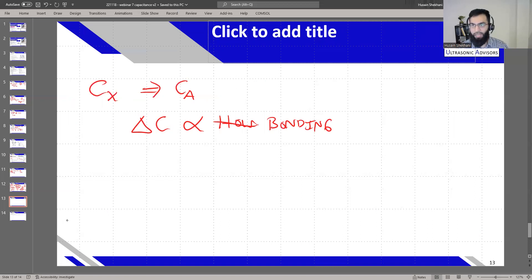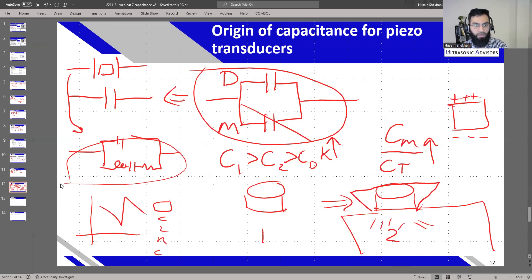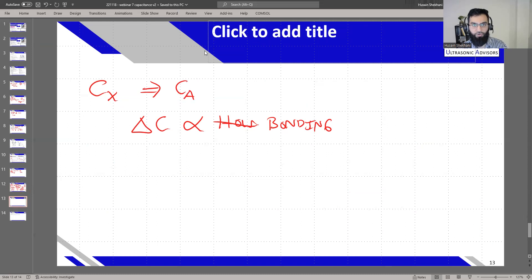One practical application: measure capacitance of the crystal before assembly, then measure capacitance after assembly. The change in capacitance can be correlated to bonding condition. Generally, the better the bond, the lower the capacitance — though it won't reach zero because the mechanical component is never fully eliminated. So whenever you assemble — whether in a bolt-clamped Langevin transducer or otherwise — the capacitance is reduced, and that reduction becomes a way to judge assembly quality. If two identically built transducers show different capacitance changes, that points toward an assembly issue.